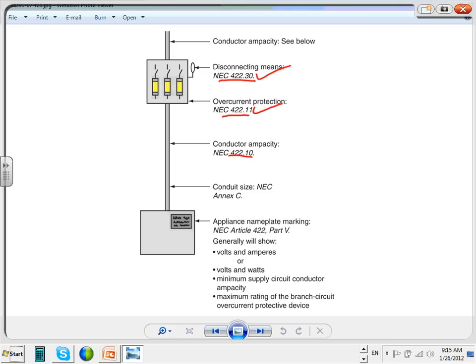The conductor size is 1.25. If it's an appliance that doesn't have a motor, they take 1.5, I believe, times the full load current, if it's more than 13 amps. The disconnect, which I would, and the conductor 1.25, size the disconnect exactly like a motor, 1.15 times full load current. That's for an appliance that doesn't have a motor, a heater that doesn't have a motor, and so forth. All appliances, all motors, all machines must have a disconnect, overcurrent protection device and controller.